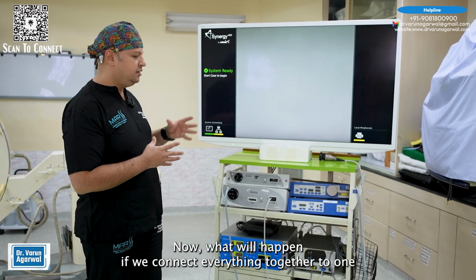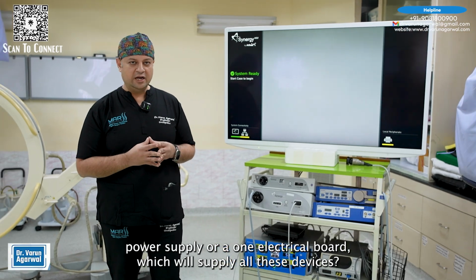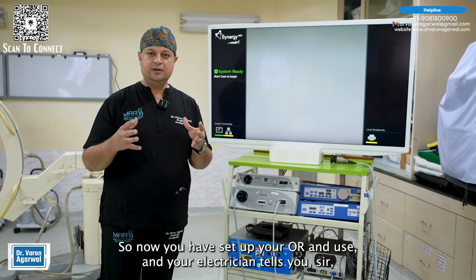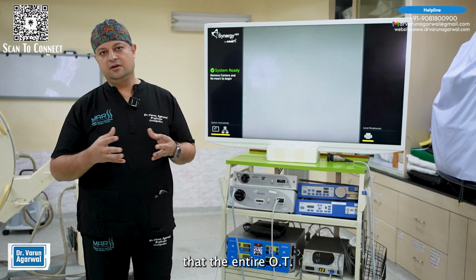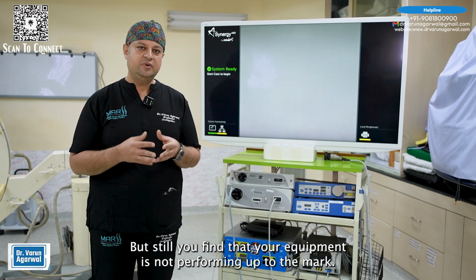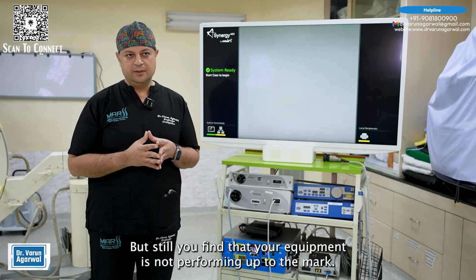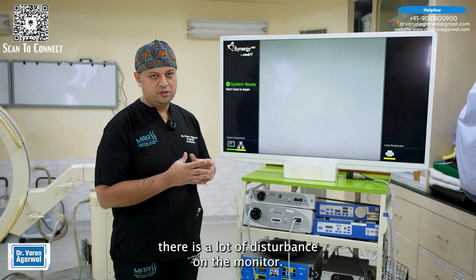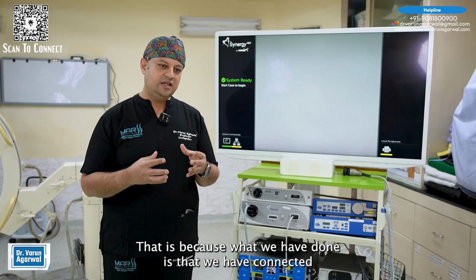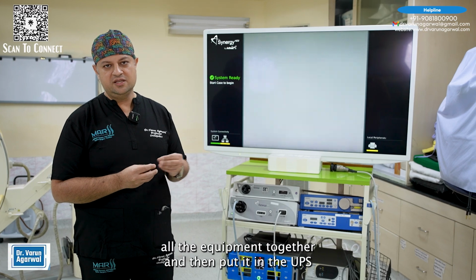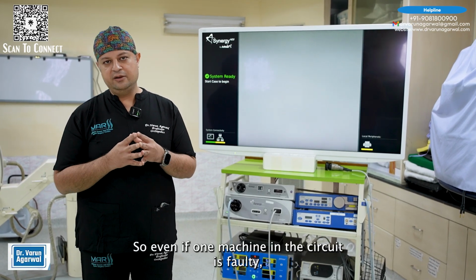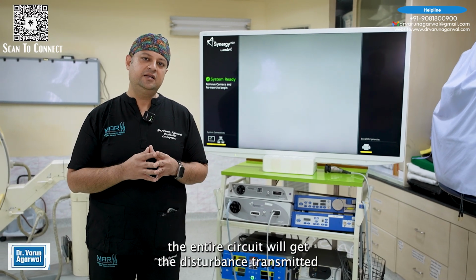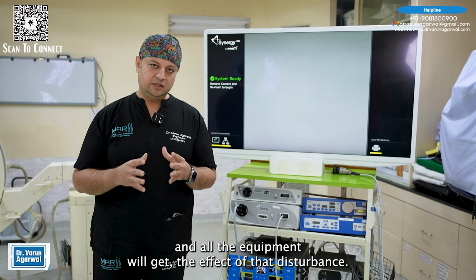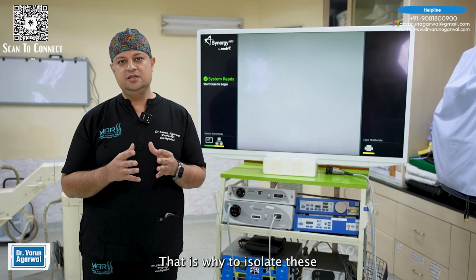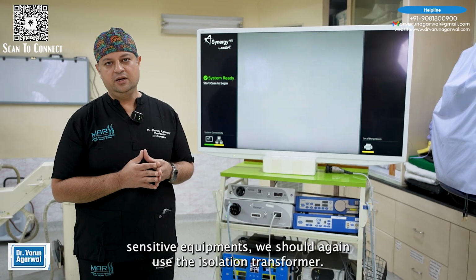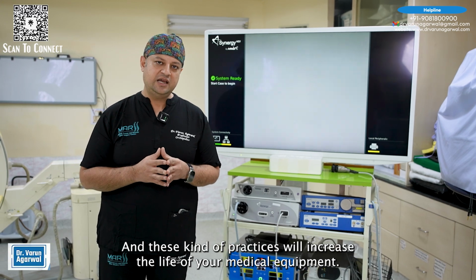Now what will happen if we connect everything together to one power supply or one electrical board which will supply all these devices? So now you have set up your OR and your electrician tells you, sir, the entire OT is supplied by a CVT line or a UPS line, but still you find that your equipment is not performing up to the mark, it is getting damaged, or when you switch on the cautery there is a lot of disturbance on the monitor. That is because we have connected all the equipment together and then put it on the UPS or the power supply. So even if one machine in the circuit is faulty, the disturbance will be transmitted through the entire circuit and all the equipment will feel the effect of that disturbance. That is why, to isolate these sensitive equipments, we should again use an isolation transformer, and these kinds of practices will increase the life of your medical equipment.